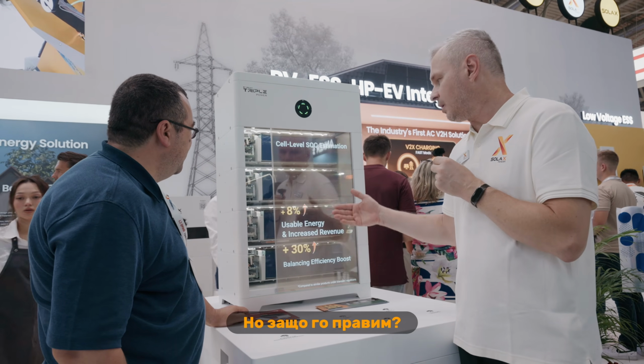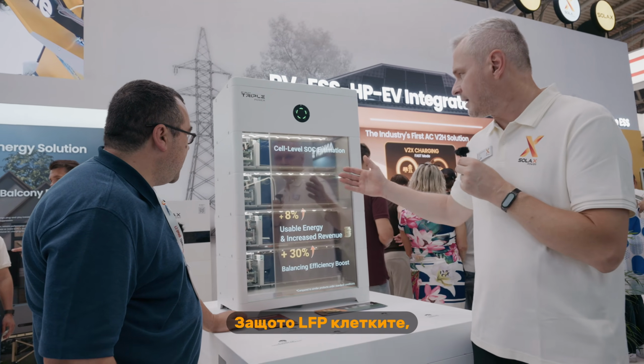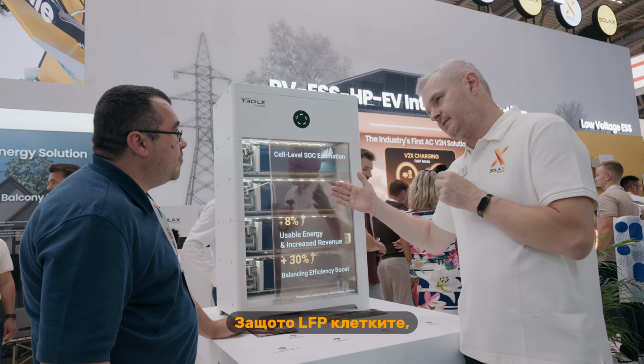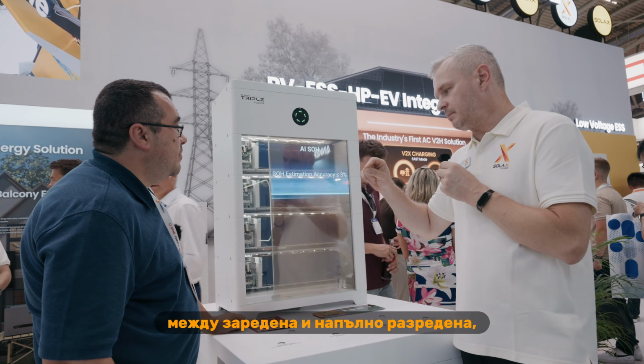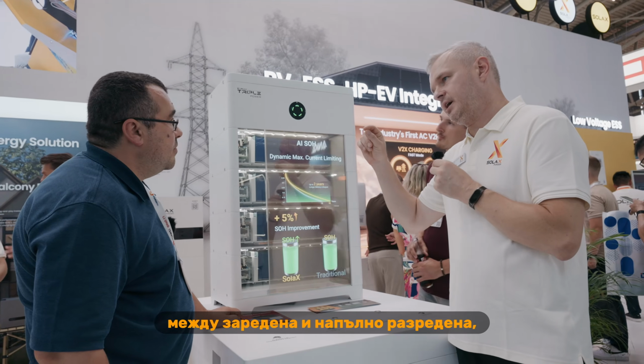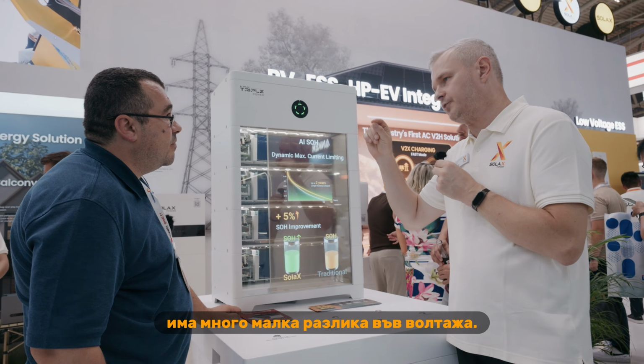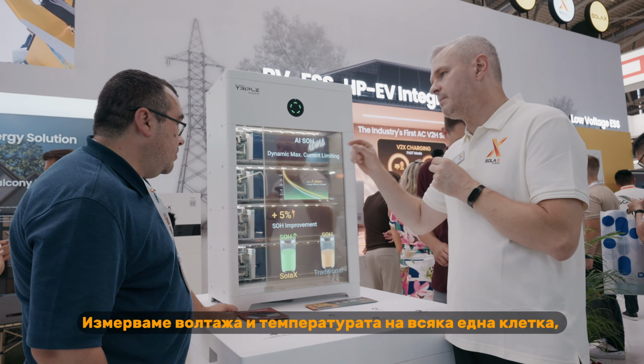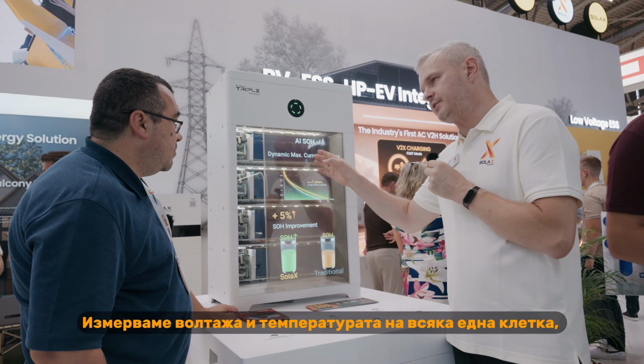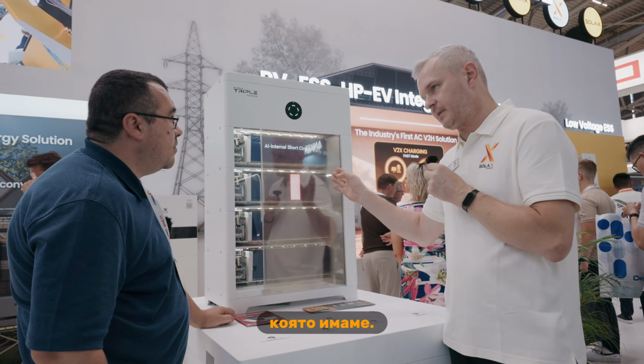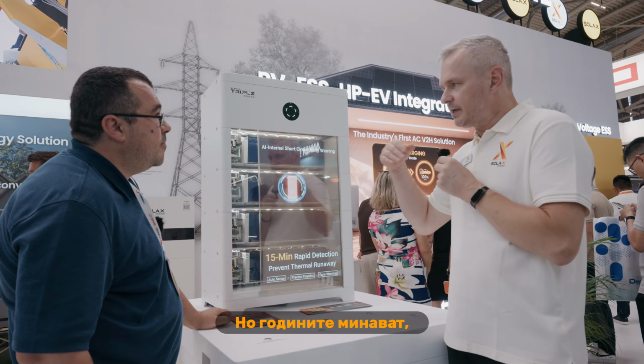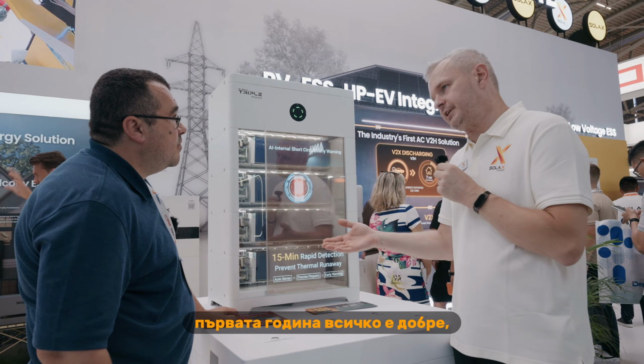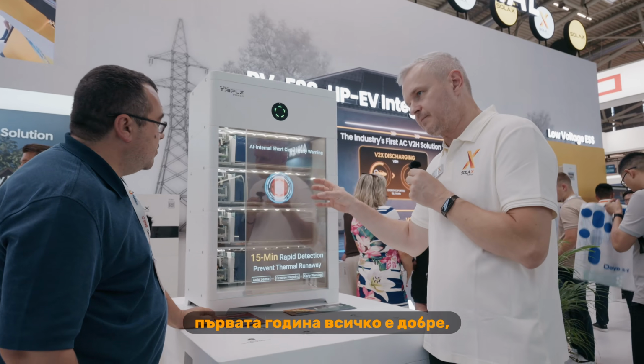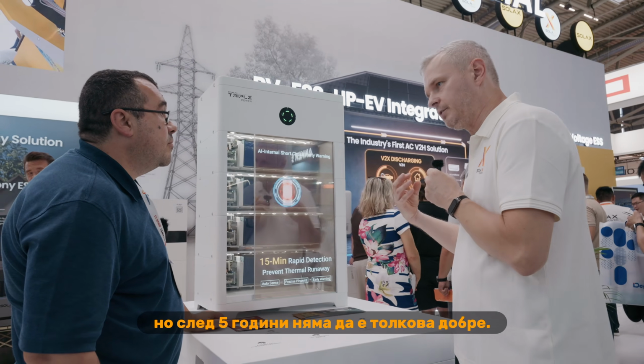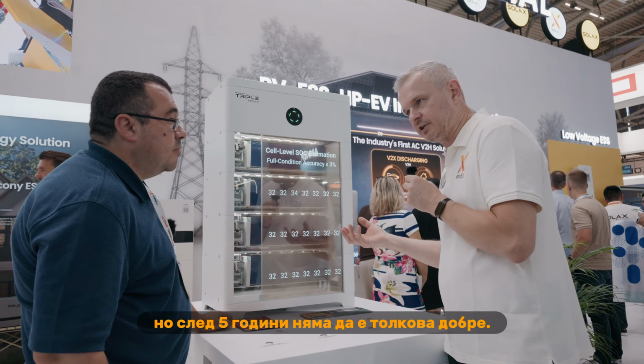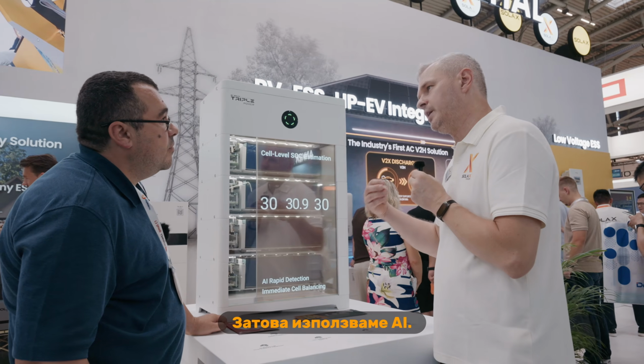But why do we do it? Because with LFP battery cells, between discharged and fully charged there is really a small difference in voltage. We measure the voltage and temperature on every single battery cell we have. But as the years go by - in the very first year your algorithm is very good, but after 5 years your original algorithm may not be that good. That's why you have AI.